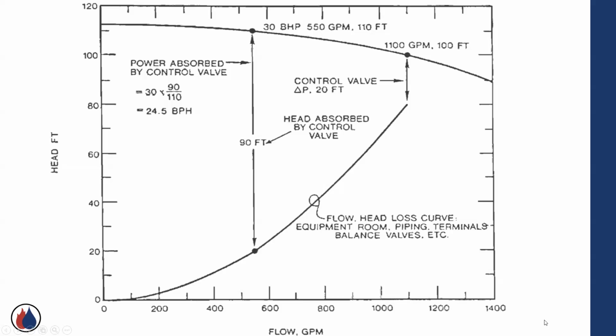This is what they would refer to as the flow head loss curve, and that's based on equipment, piping, terminals, balance valves, all right here. This 20 feet of control valve head loss is fixed. That's not changing, the 20 feet. But the other 80 feet is variable. At design flow, that's what it is: 80 feet plus the control head of 20 for a total pump head of 100. As the valves close, the pump moves which way? It moves to the left.